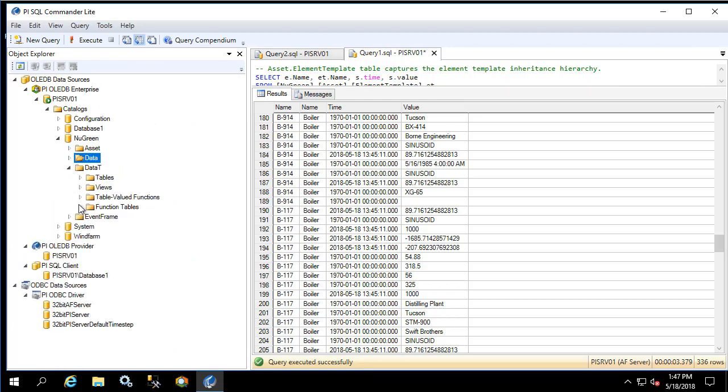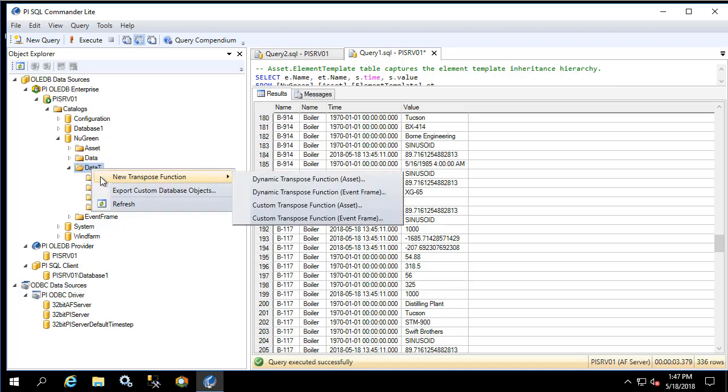As mentioned in a previous video, the data T schema is blank by default. To create a new transpose function, right-click on data T, then new transpose function. As seen in the menu, the two options are dynamic or custom, and asset or event frame. Asset corresponds to element templates whereas event frame corresponds to event frame templates. Dynamic versus custom is the difference between all attributes created from the template — which is dynamic — versus being able to specify which attributes you would like to add to the transpose function output, which is custom.